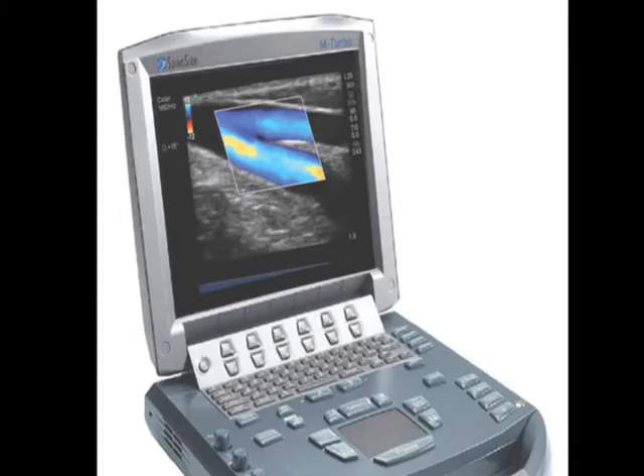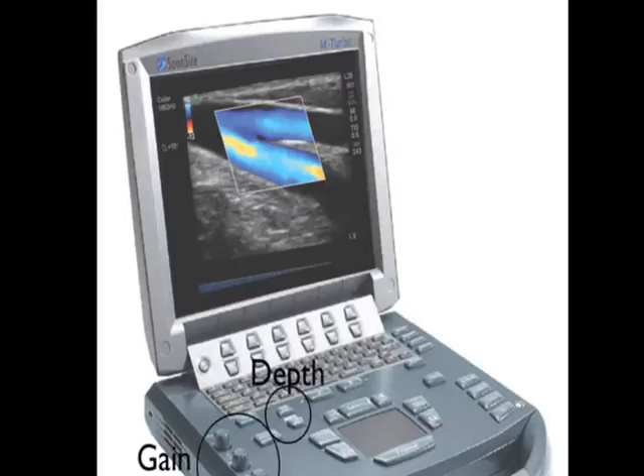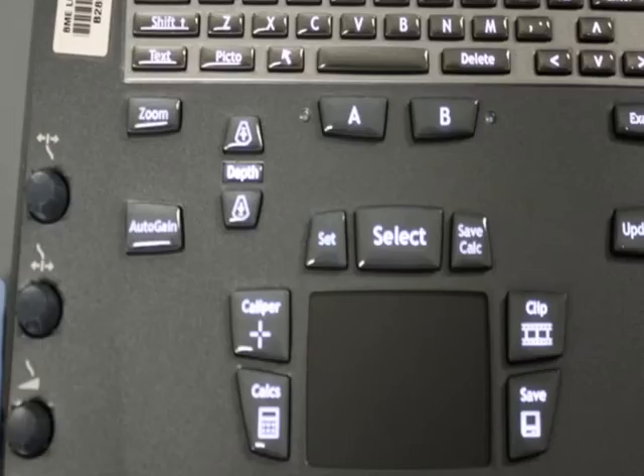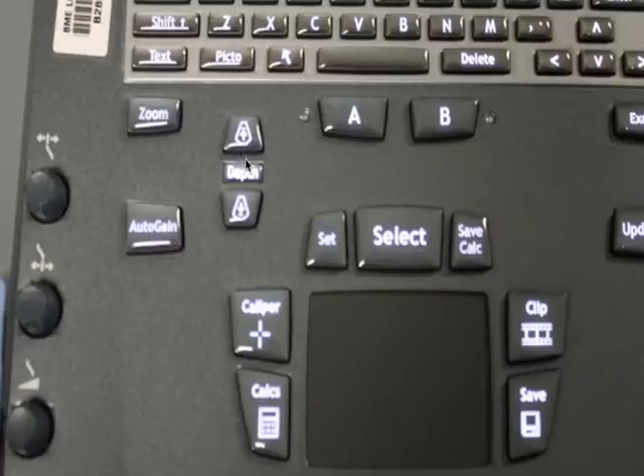As you know, the two main controls most helpful to you in ultrasound on any machine are going to be the depth and the gain controls. Let's see what these look like on the M-Turbo. The depth is fairly straightforward, featuring a decreasing depth button here and an increasing depth button here.